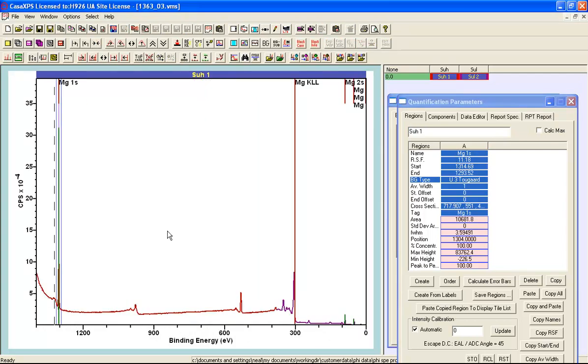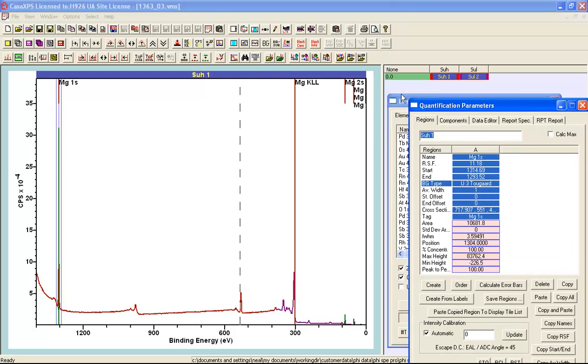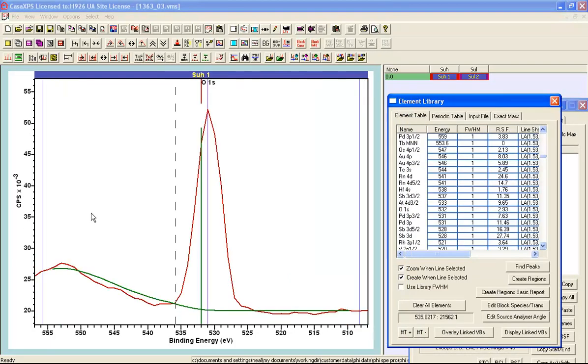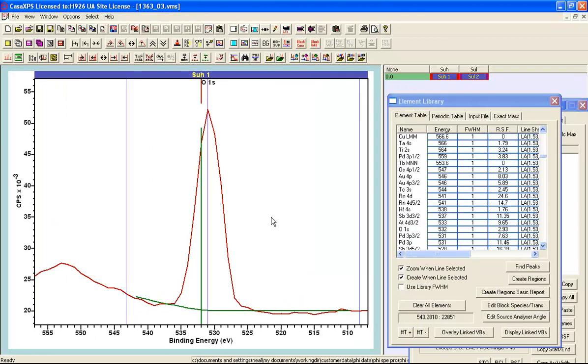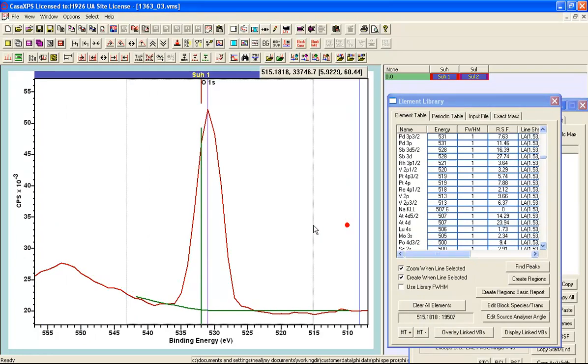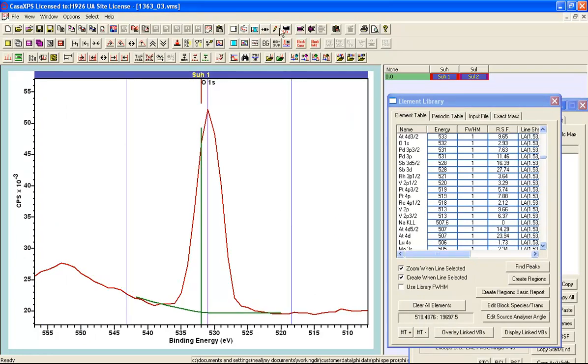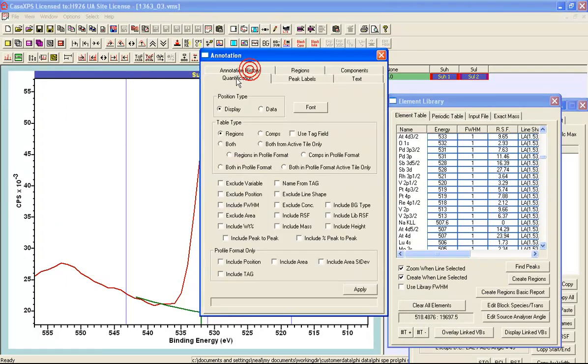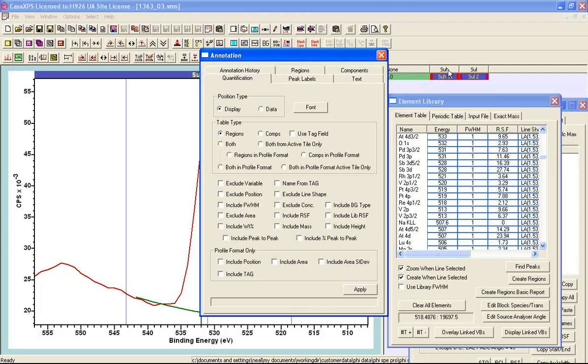If I zoom out and then I select the oxygen 1s, create a region here, and then I will put up a quantification table. I am going to use quantification rather than regions and this is because I want to be able to quantify not just within the one VAMAS block. I use the quantification option because when I select multiple VAMAS blocks in a row then the data within the row will be quantified one against the other. So here I am going to exclude the area and I want to include the relative sensitivity factor. Now press apply.